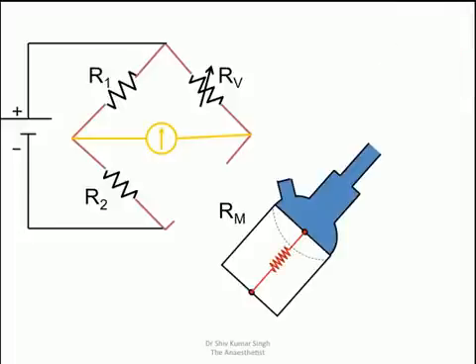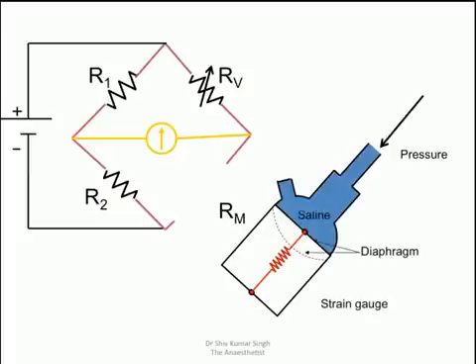The transducer basically is part of a Wheatstone bridge. And the present transducers they are calibrated in the factory and so we don't have to calibrate them.